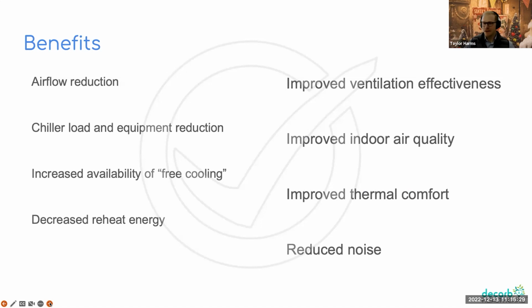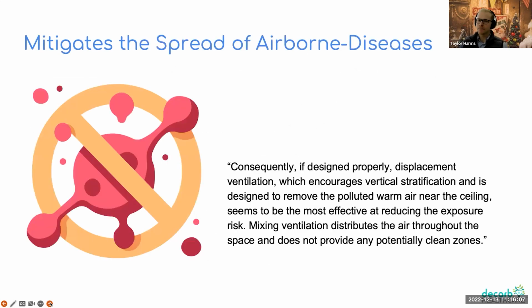There are many benefits of displacement ventilation, obviously. Reduced airflow, reduction in equipment energy. There's an increase in the availability of free cooling, less noise, decreased reheat, improved indoor air quality, which is of utmost importance for healthcare spaces especially, and improved thermal comfort as well, so you don't have people constantly changing the thermostat trying to cool the room off. And it mitigates the spread of airborne diseases because it's much more effectively able to push the contaminated air towards the returns and moving it away from the breathing zone.